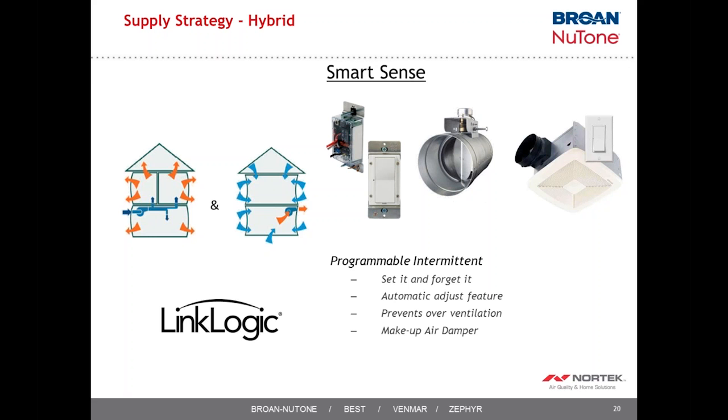One important wiring note: all exhausting appliances using this system should be on the same electrical phase (bus side). Since 240V comes into the house and splits into two 120V legs, the signal should not have to pass through a 240V appliance to reach the panel and then the damper. Keeping everything on the same phase ensures reliable communication between the switches and the LinkLogic controller.